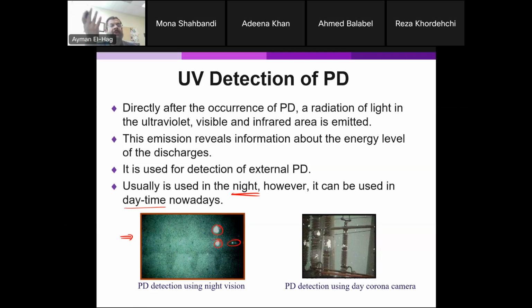Now, there's no 100% dark. There is always a slight light there. So these cameras basically try to magnify that light so that you can see it. But this is a limitation because you can do it only at night, meaning that you have to send the worker on overtime. But now with the daytime corona cameras, you can see partial discharge clearly during the daytime, so you don't need to use that. But as you will see here, it's a very expensive camera.